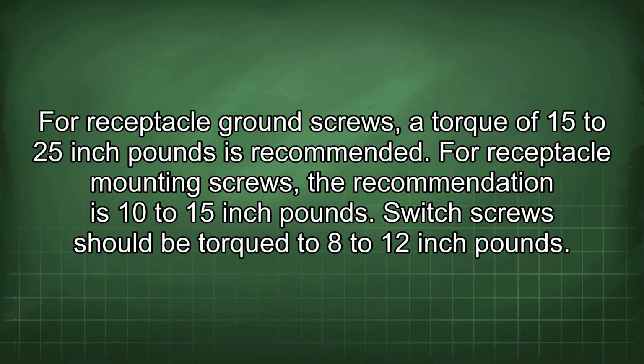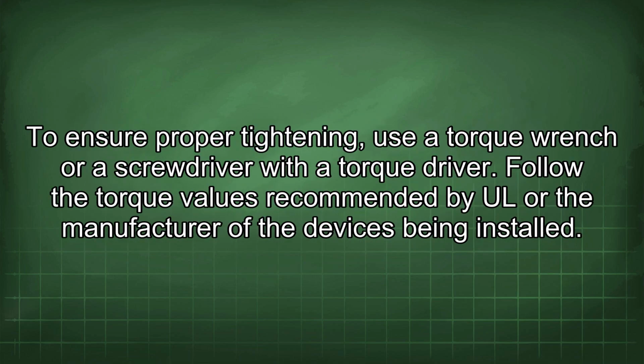For receptacle mounting screws, the recommendation is 10 to 15 inch-pounds. Switch screws should be torqued to 8 to 12 inch-pounds. To ensure proper tightening, use a torque wrench or a screwdriver with a torque driver. Follow the torque values recommended by UL or the manufacturer of the devices being installed.